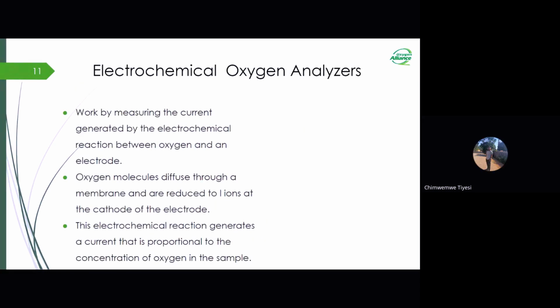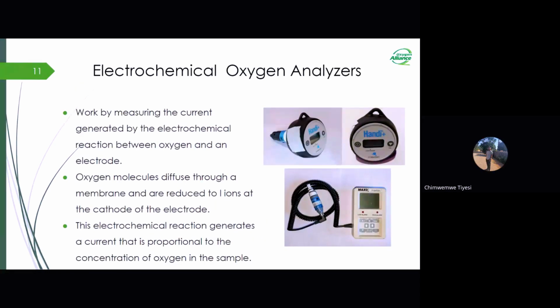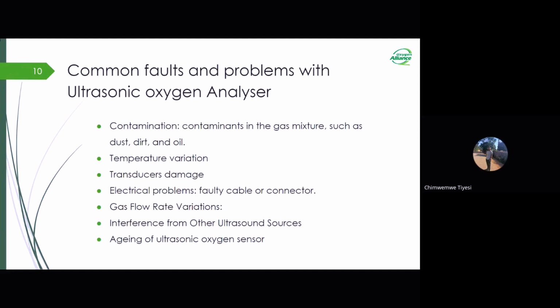One other thing that can affect the readings on the oxygen analyzer, which of course may not be common, is interference from other ultrasonic sound sources. In hospitals, if you have other machines that are producing ultrasound waves, you can have problems in the reading of your sensor, because this can interfere with what the sensor is reading inside. So identifying and mitigating such interference is very important in the medical field.